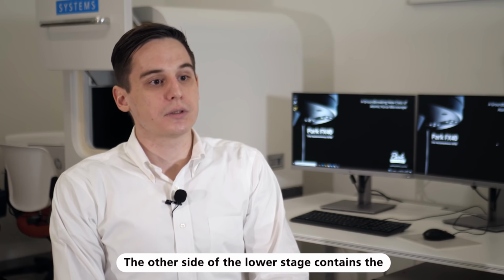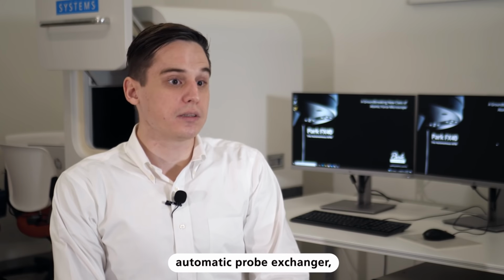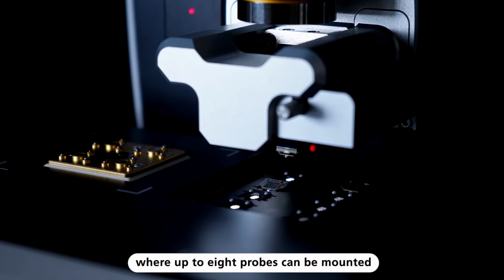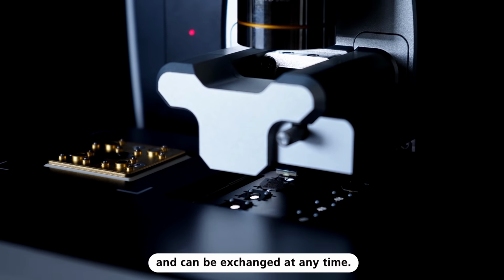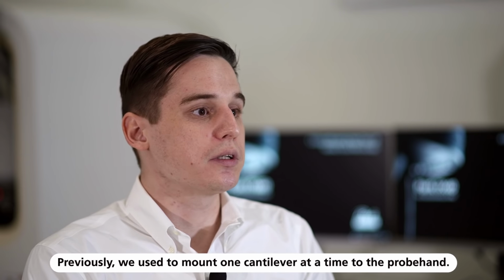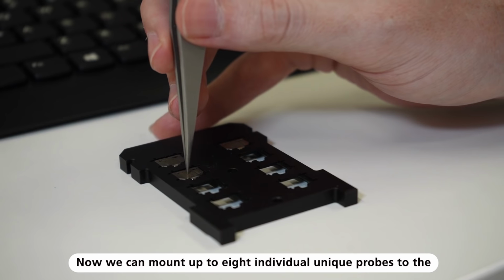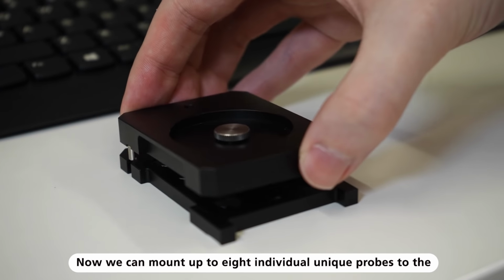The other side of the lower stage contains the ATX, or automatic tip exchanger, where up to 8 probes can be mounted and can be exchanged at any time. Previously, we used to mount 1 cantilever at a time to the probe hand. Now we can mount up to 8 individual unique probes to the automatic tip exchanger with the cassette.